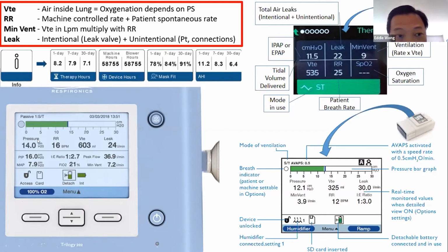For the basic BiPAP ventilator, they also provide these 4 additional information. We call it therapy hours. Last night, how many hours of use have you been using? For the past 1 week, in average, how many hours of use? In the 1 month, how many hours of use? The more you use, of course, it will help you more, correct? And this one here is to tell you if the mask fits. When you're using this BiPAP device, if the mask fit is below 90%, there's a time you need to check your mask fitting or change to a new mask.